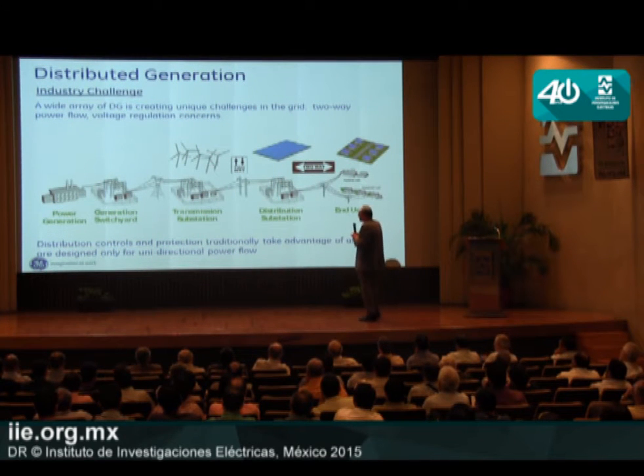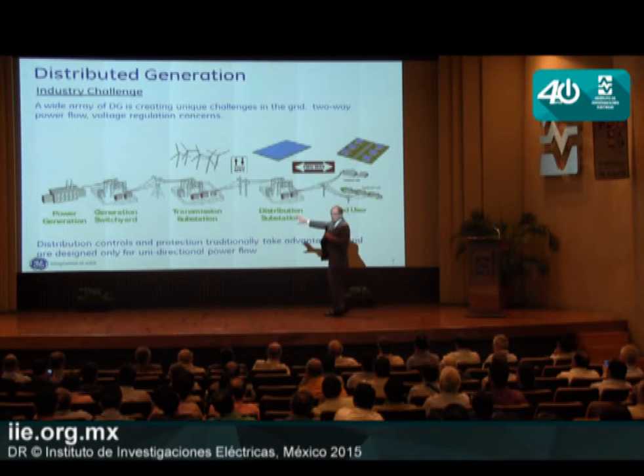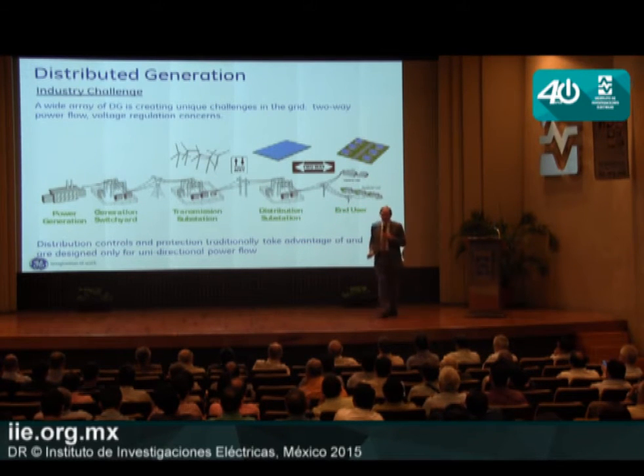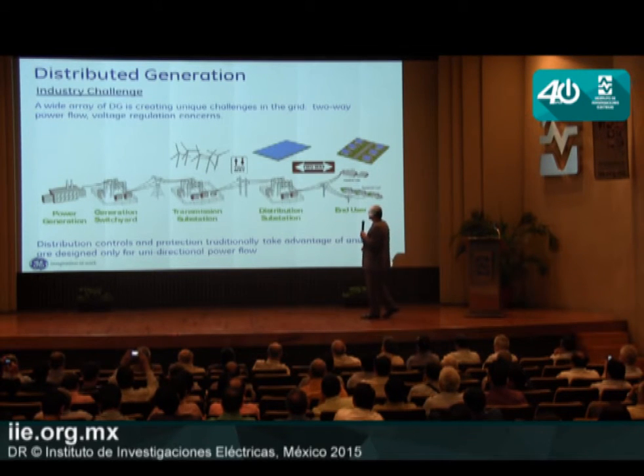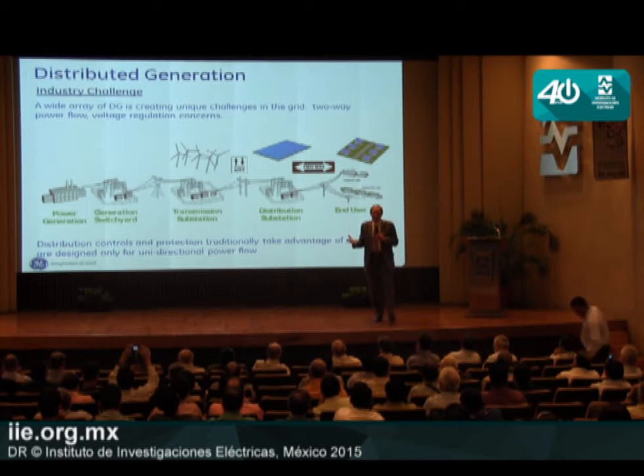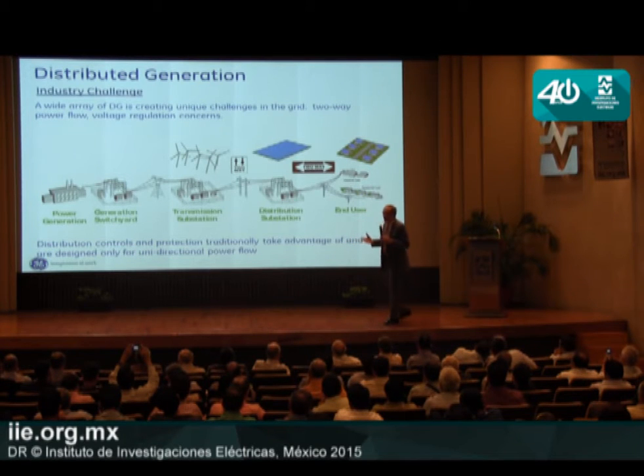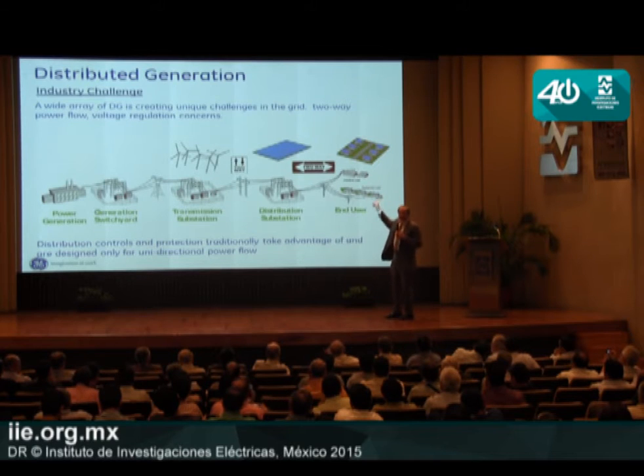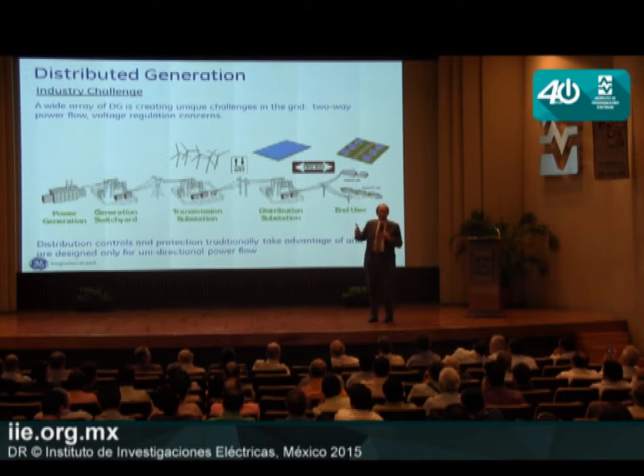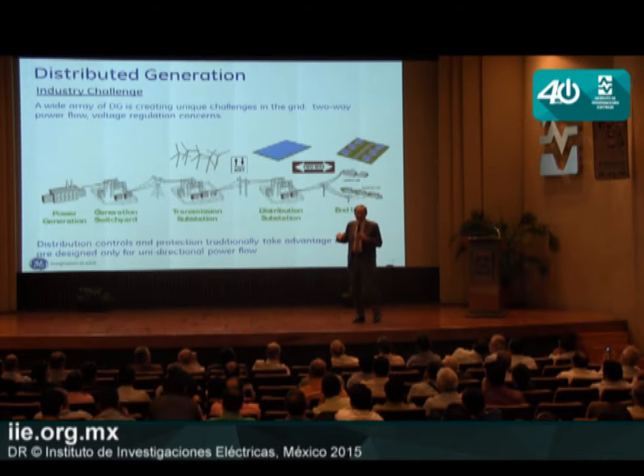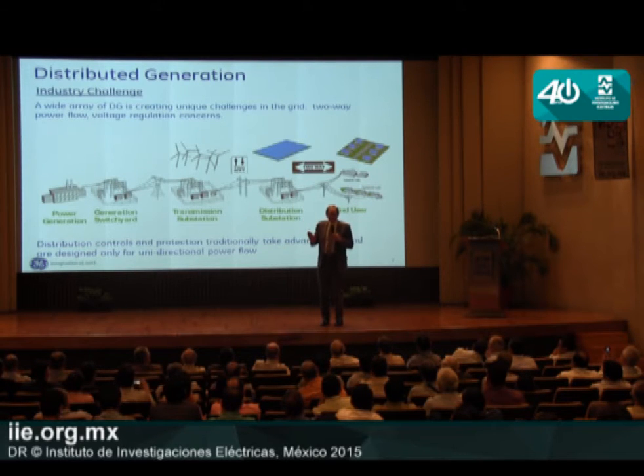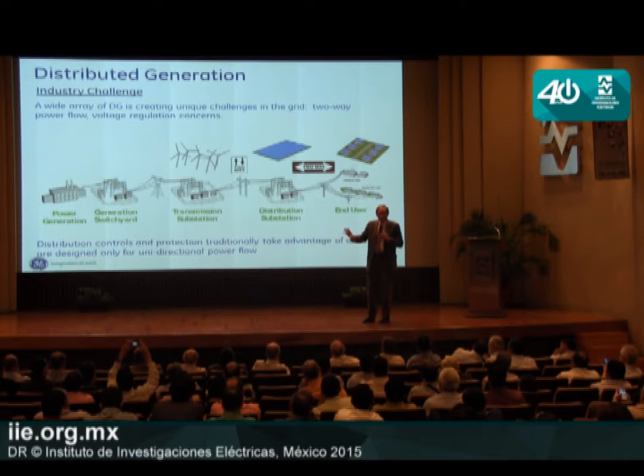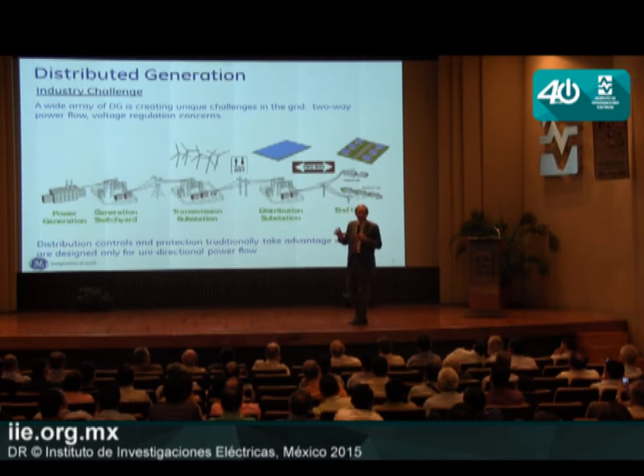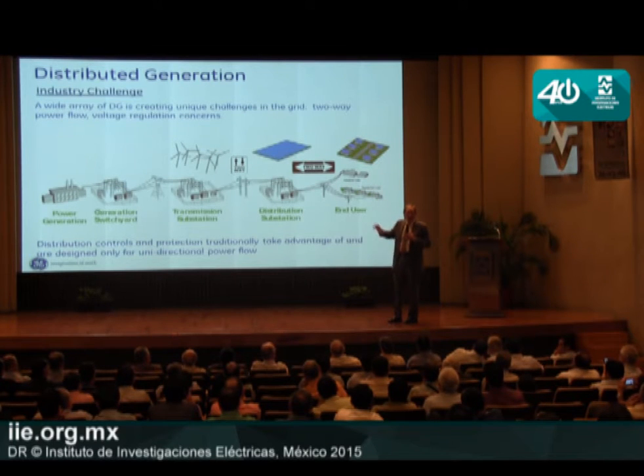So let's look at renewables. We can integrate renewables at the transmission level, the distribution level, or at the end user level - three different levels. What challenges does renewables give us? Operational challenges with intermittency, but also on the distribution system. We designed the distribution system for electricity flowing in one direction, from source to load. Many distribution systems are radial in topology: the feeder brings electricity to the customers, and when we reach the last customer, the feeder ends. There's no loop, no tie point to another feeder. It's radial, a very simple architecture - one-way flow.